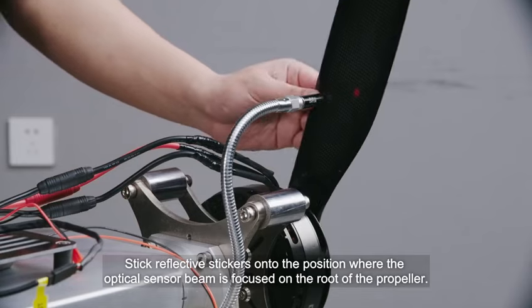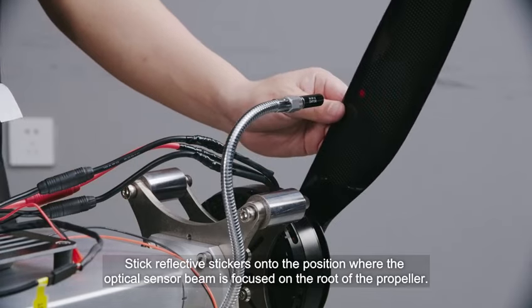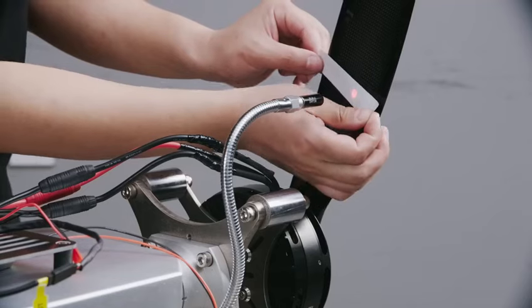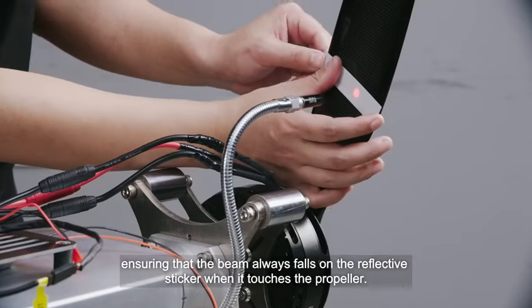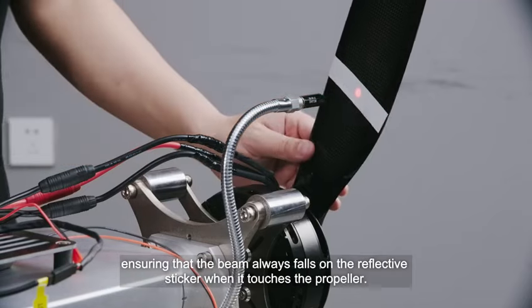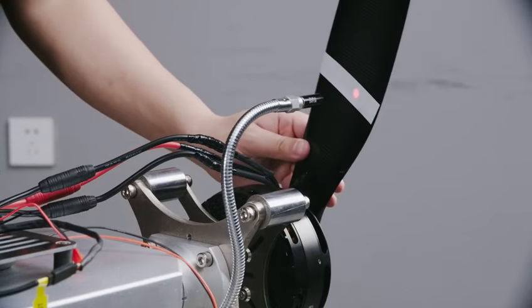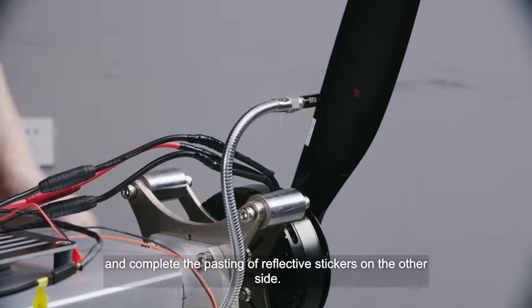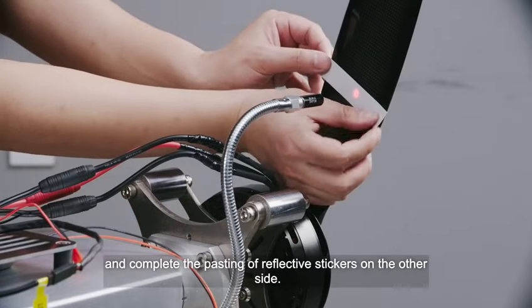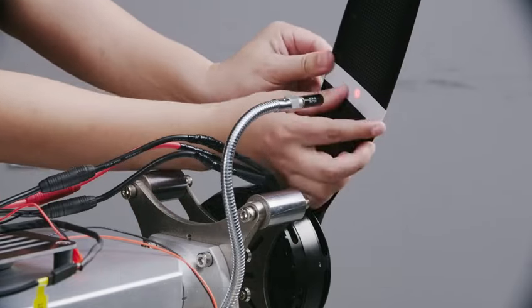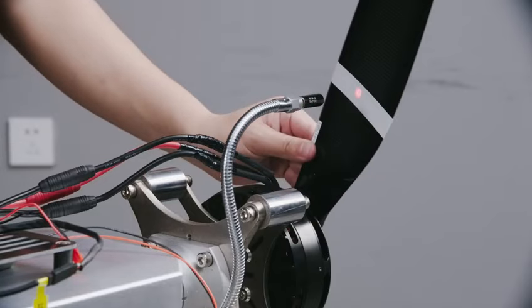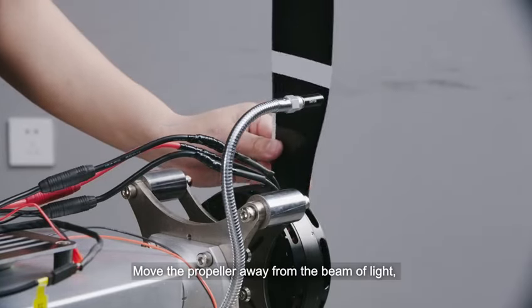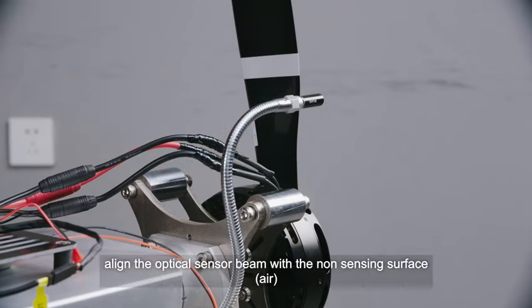Stick reflective stickers onto the position where the optical sensor beam is focused on the root of the propeller, ensuring that the beam always falls on the reflective sticker when it touches the propeller. Rotate the blade and complete the pasting of reflective stickers on the other side. Move the propeller away from the beam of light. Align the optical sensor beam with the non-sensing surface.